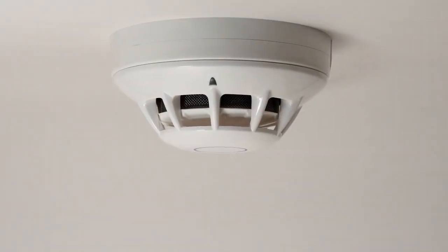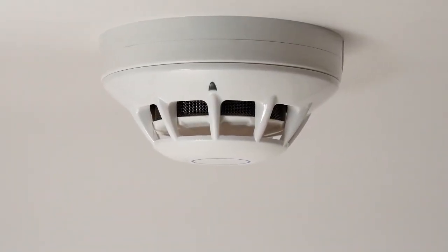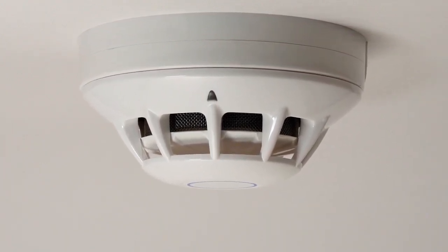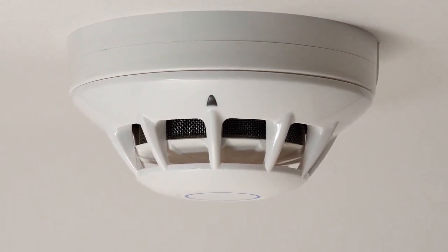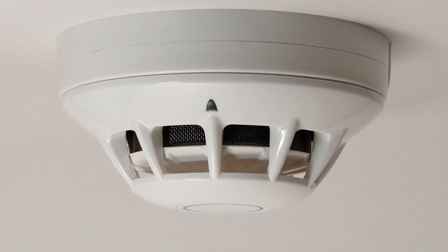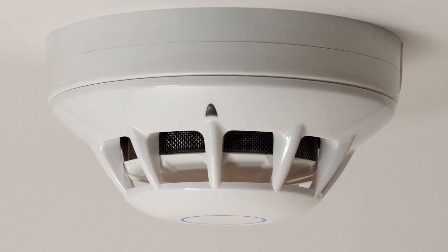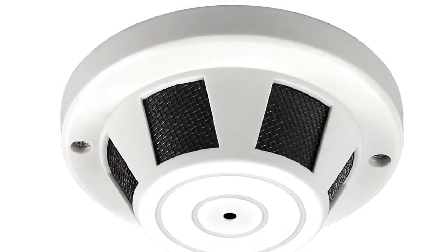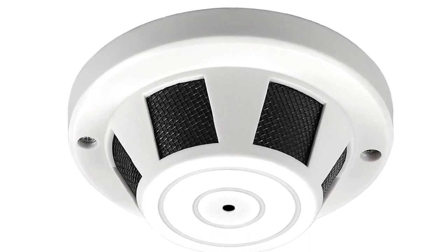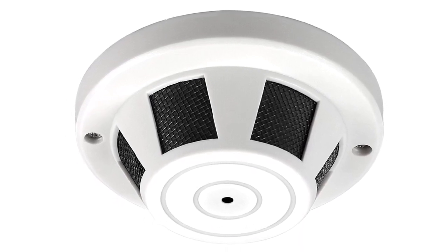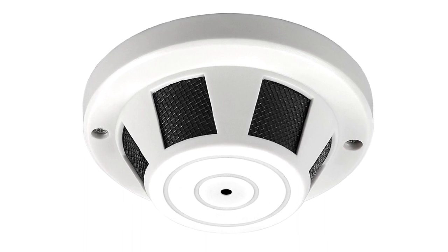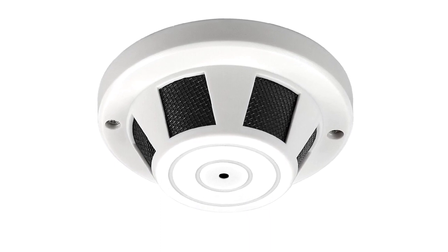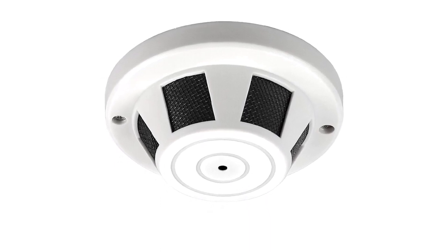Ionization detectors use ionizing radiation from a material known as americium-241. Ionizing radiation is simply radiation from substances that can free electrons from an atom or molecule, the net result being ions that have a specific electric charge of either positive or negative. The detectors use a small amount of americium-241 contained in a small chamber. This chamber is made up of two oppositely charged metal plates that are kept a small distance apart. When the alpha particles interact with the air in the chamber, they produce ions. The positively charged plate attracts the negative ions, and the negatively charged plate attracts the positive ions. This system creates a small electric current.